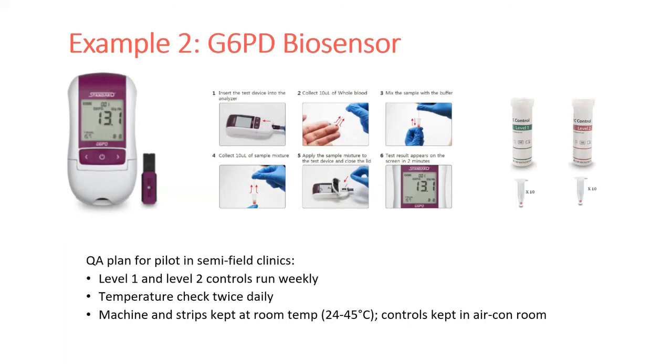This tool also comes with 2 levels of control samples. They are in the form of a lyophilized ball shape, and they can be diluted in the buffer and then tested exactly as a normal sample. We have used this biosensor extensively in our laboratories, but we want to try to bring it to the community.